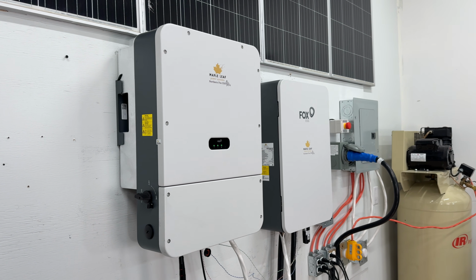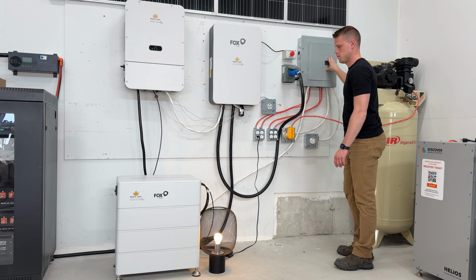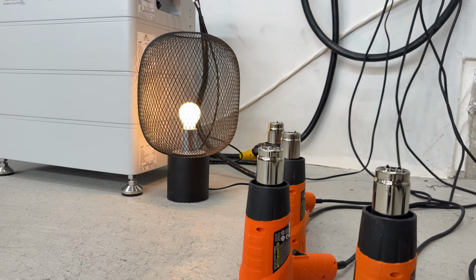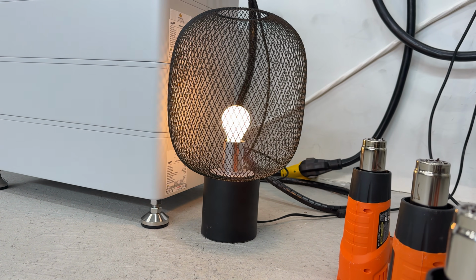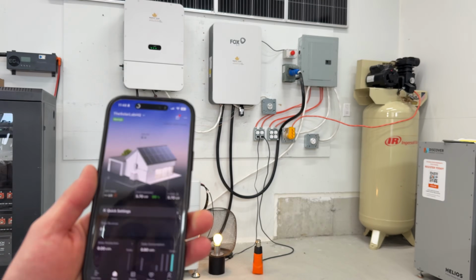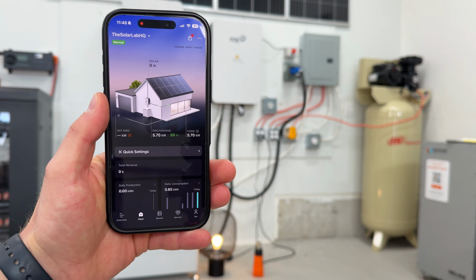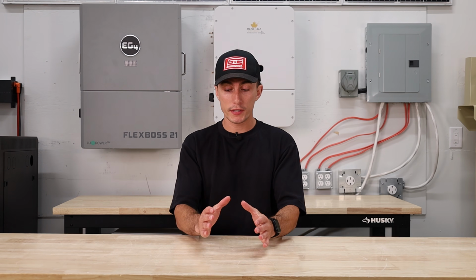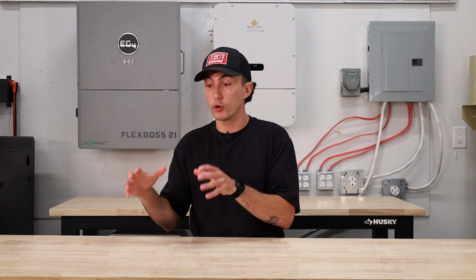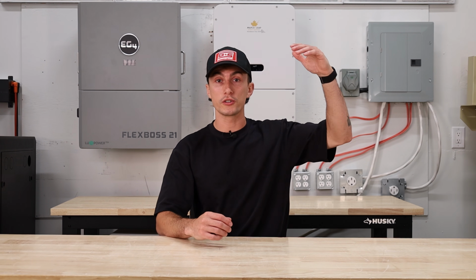In our testing, it was hard to say exactly how it performed. In terms of numbers and results, it did really well, hit all our benchmarks. But did it output the 12,000 watts? No, because we didn't have the right amount of batteries, and people weren't understanding that. Every time you take away or add a battery, your high voltage system works at a different load range. With a 48 volt system, you buy as many batteries as you need for your storage capacity requirements, like however many days of backup you want. With a high voltage system, you're literally capped by law depending on where you are - I think in Canada and Europe it's 5 batteries, and in the States it's 8 or something like that. Once you stack a certain amount of batteries, you're past the voltage allowance for the UL certification, and it's literally illegal to keep going. It's a lot more confusing than the 48 volt stuff.